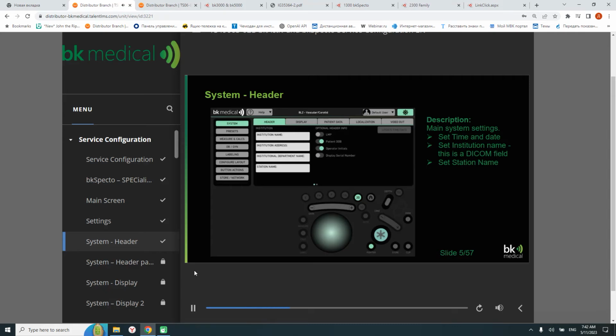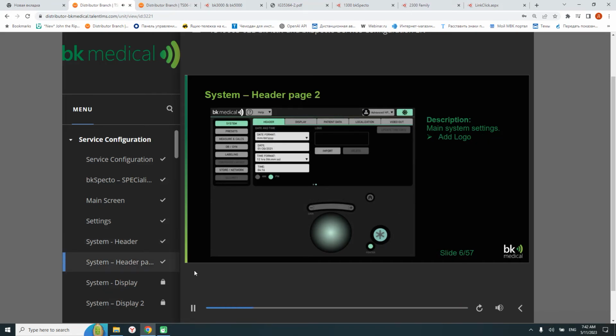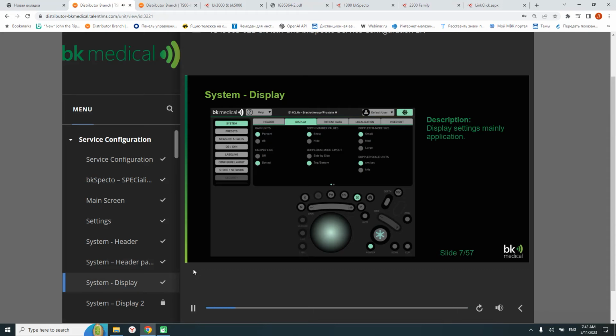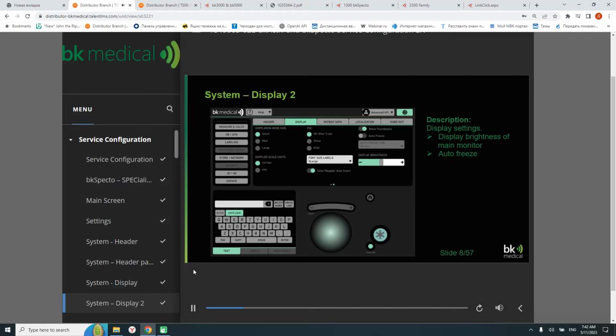System header is where time and date can be changed. The institution name can be set and used as a DICOM tag. Slide to page 2 of the header where it's possible to import a logo, which will be shown in the top left corner. The Display tab contains application settings related to the display, such as gain unit shown on the screen. Page 2 of the Display tab has more application-related settings. This is where the display brightness of the main monitor can be changed. Auto freeze is a timer function where the user can choose when the system should freeze automatically.